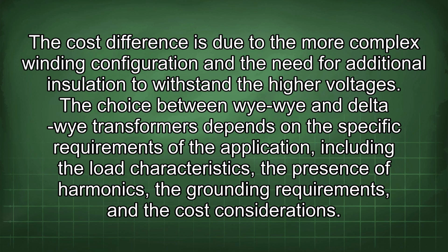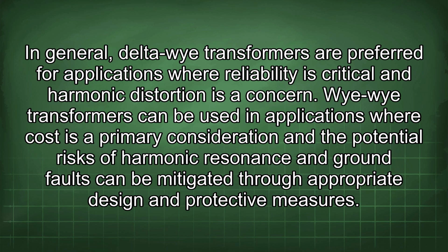The choice between Wye-Wye and delta-wye transformers depends on the specific requirements of the application, including the load characteristics, the presence of harmonics, the grounding requirements, and the cost considerations. In general, delta-wye transformers are preferred for applications where reliability is critical and harmonic distortion is a concern. Wye-Wye transformers can be used in applications where cost is a primary consideration and the potential risks of harmonic resonance and ground faults can be mitigated through appropriate design and protective measures.